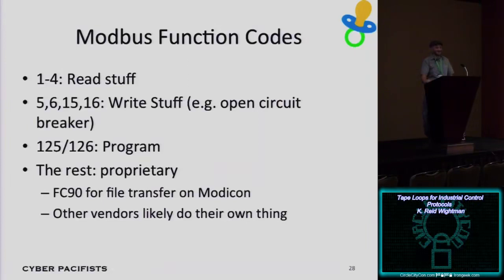Function code 90 has all kinds of neat features. You can even tell the PLC to stop processing using that function code. It's one of those other functions the Modbus spec allows. The spec defines 1 through 4, 5, 6, 15, 16, 125, and 126; anything else is up to you. If you want a vendor-specific function code, you use one of those other numbers, and that's what Schneider did with function code 90. I'm sure other vendors do similar things.